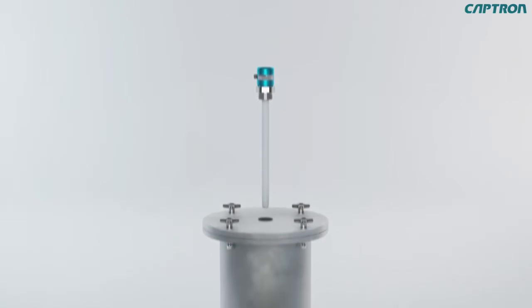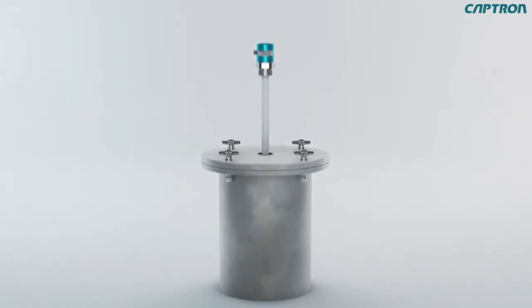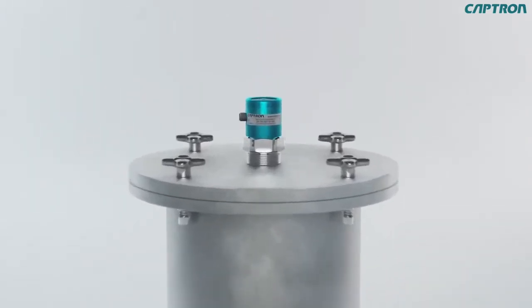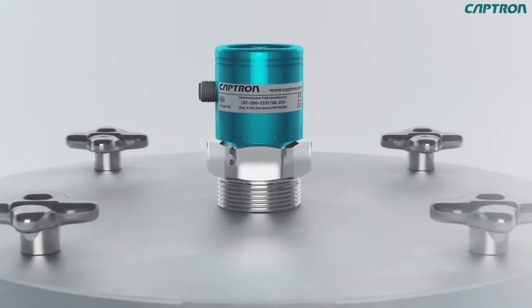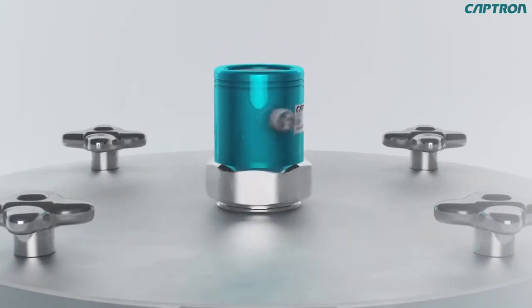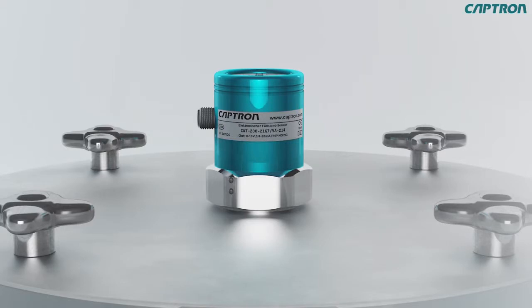Welcome to the adjustment instructions of the fill level probe VA214. First, the instructions for installing the probe. Screw the probe into the tank cover. Use a 1.5 mm Allen key to loosen the stud screw with 2 revolutions to the left.